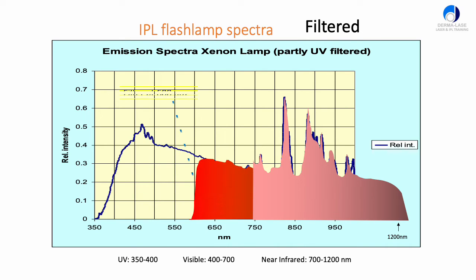We don't necessarily want all that energy when we're treating targets in the skin, so with an IPL we'll put in a filter, maybe something like this at 600 nanometers. That'll block all the light energy below 600 nanometers and only allow through the red and near-infrared energy between 600 and about 1200. In this way we can target specific chromophores in the skin — for example melanin — and using red and infrared light, we can target those quite safely without damaging hemoglobin in the blood vessels.